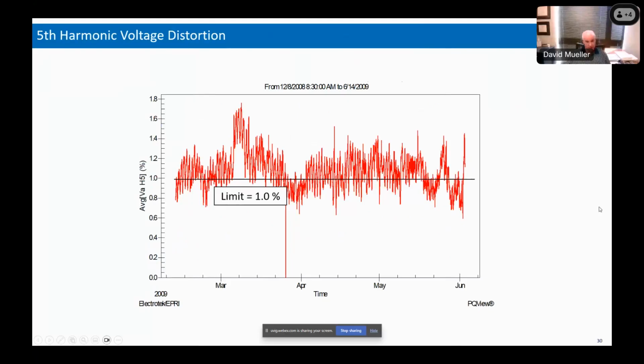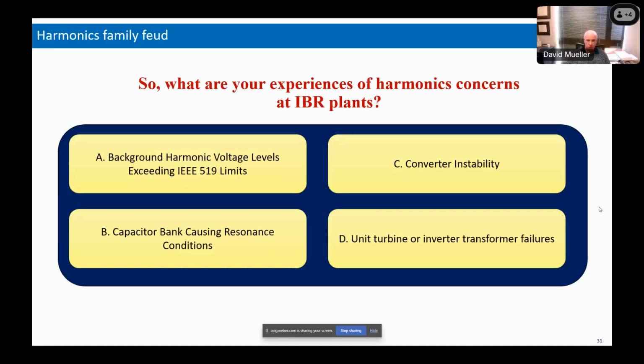However, this same site was dominated by fifth harmonic voltage, which is often the case. And so now at the fifth harmonic voltage, our limit's 1%. This occurs whether or not the wind is blowing, whether or not the wind is on. It's just a background condition. So if we want to meet IEEE 519 voltage limits, we're not going to be able to do it because of a pre-existing condition of the background voltage distortion. So those are my 4.